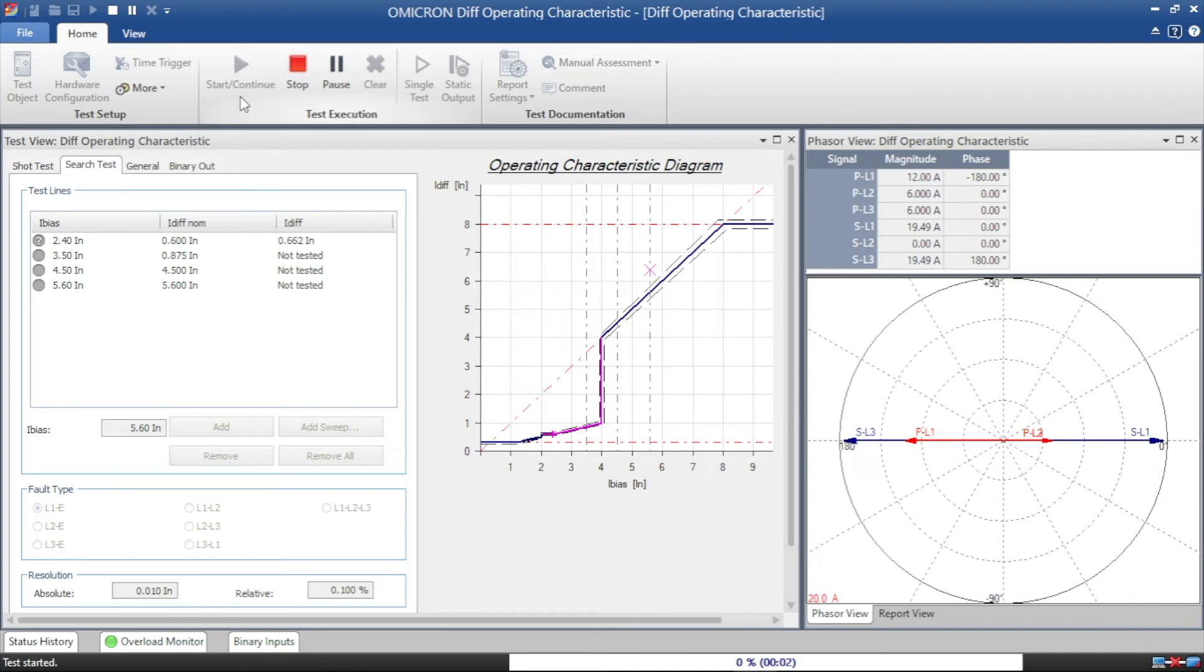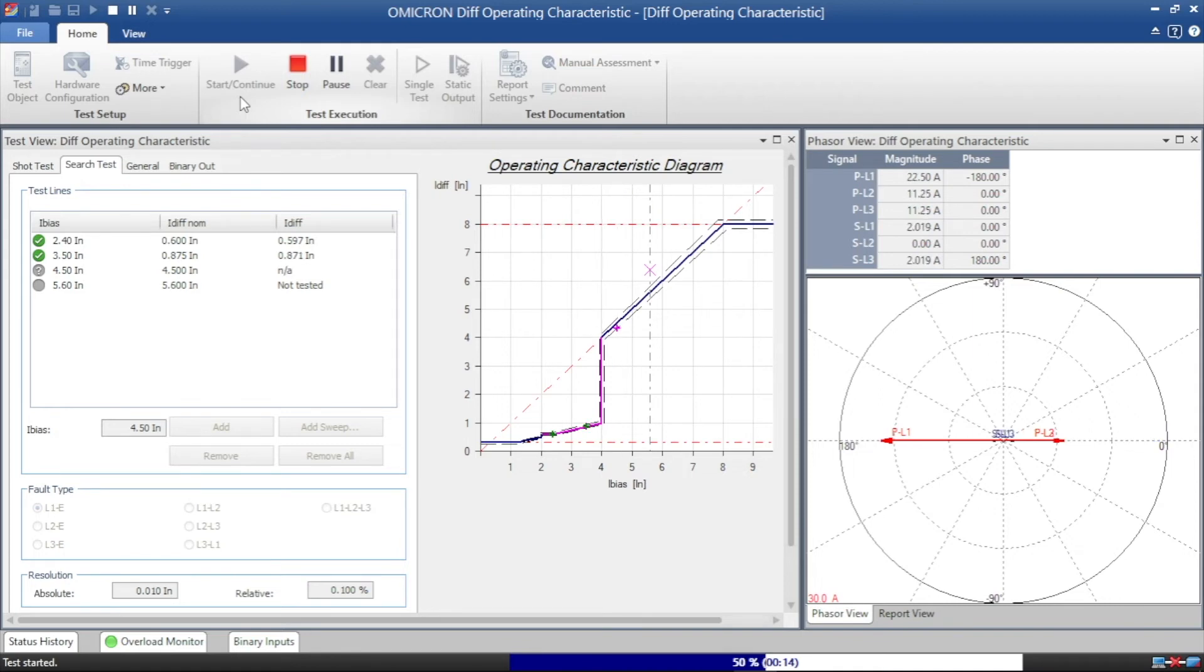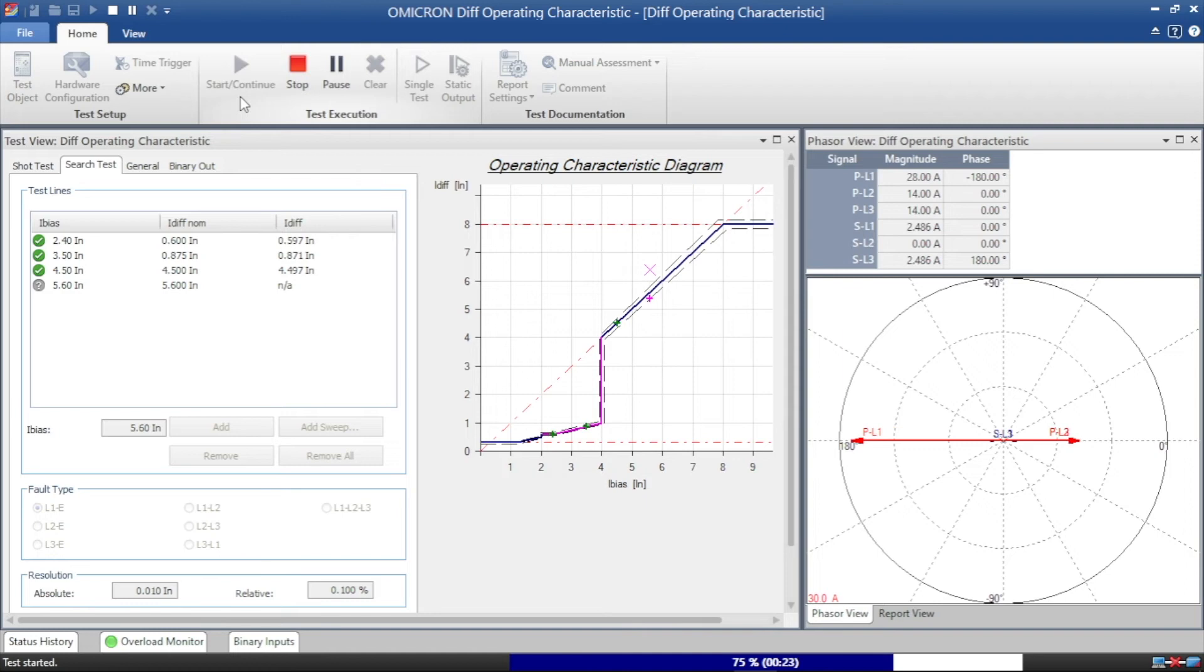Now see each value searching which point giving exact trip. We can note the value for I-bias as well as differential values. And we can enter these values in our Excel file which I already created for the slope.